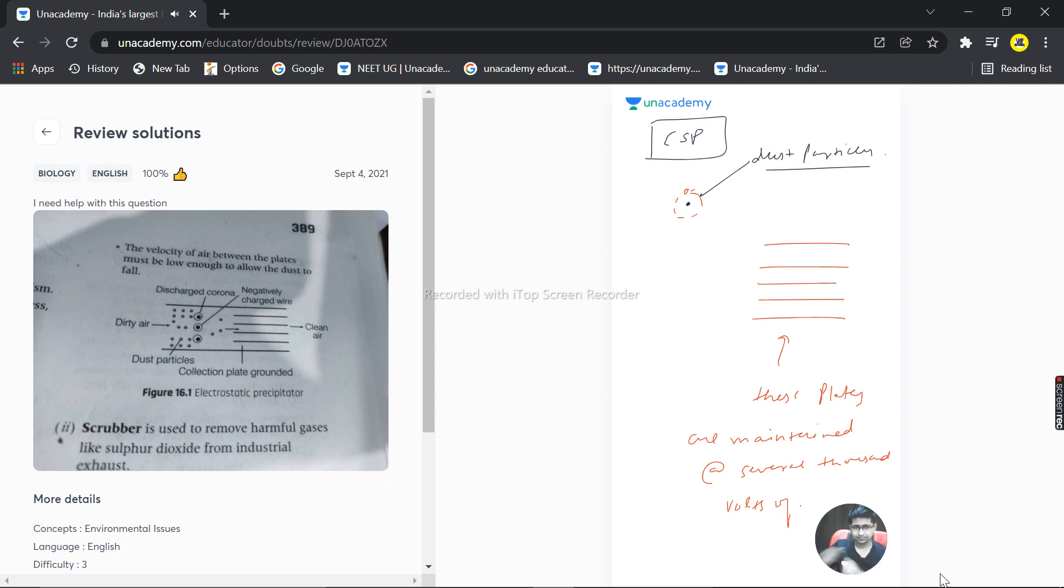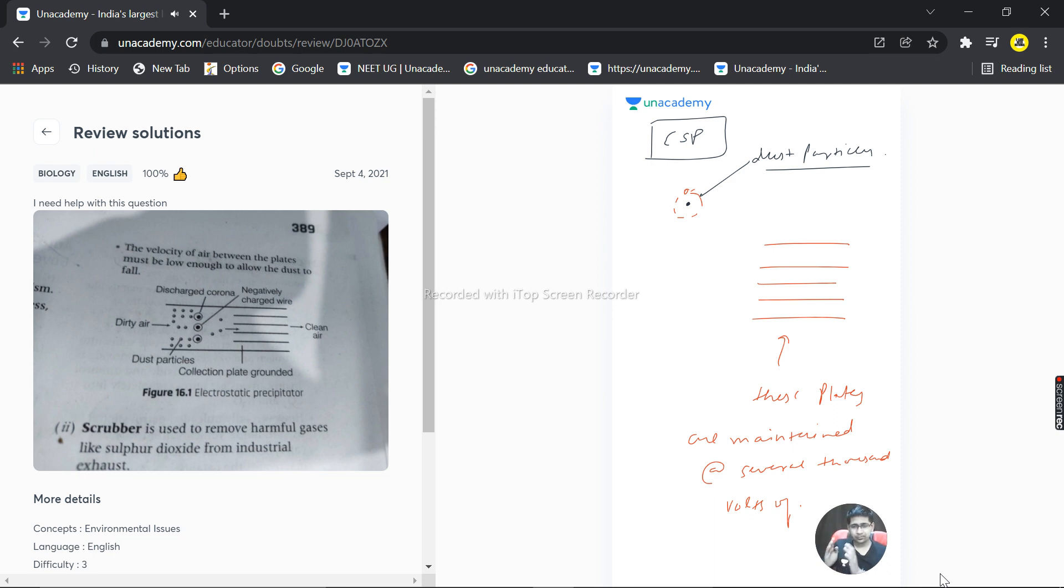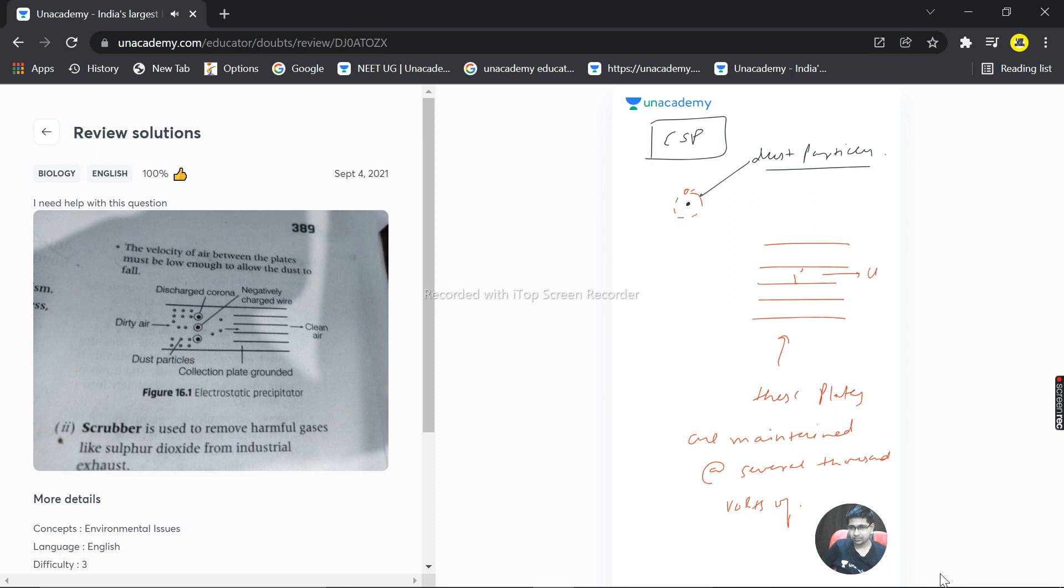And so when the dirty air is flowing through the electrostatic plates, dirt is basically, and we have to make the velocity very low. So this is a very important point, so that the dust particle with the negative charge is attached here and we get the clean air, clean air finally.